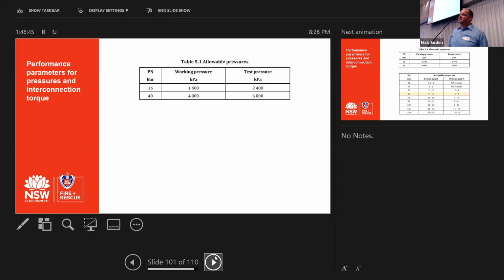Okay, performance parameters. As I just mentioned, there's 2 working pressures now. Typically forged aluminium Storz is PN16, 1600 kPa, and that will meet a test pressure of 2,400 kPa. But there's now the new variant for PN40 boosters, which will be 4,000 kPa working pressure, and they're tested to 6,000. Now, what we've been told from the German manufacturers is essentially the Storz is identical. It's actually that sealing ring that varies. But one of the manufacturers does slightly modify the shape of that ring, just so that they know you can't put a standard sealing ring into a high pressure Storz. So we'll probably address that in a variation in the next version of this standard.